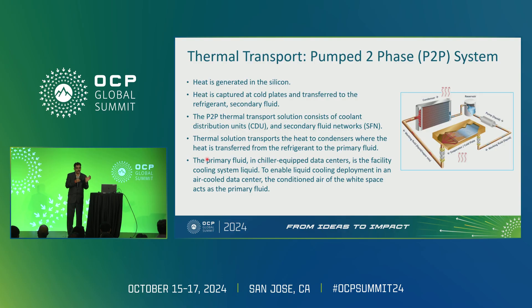A lot of people mislabel this as a compressor-based liquid cooling technology and then say the PUE or TCO is not that great. I want to make sure: if you are thinking about how it looks, it looks just like a single-phase DLC system. From the visual perspective, there is no compressor — it is a pump-based system. The system has the same ingredients: cold plate, secondary network, rack manifold, row manifold, and CDUs.